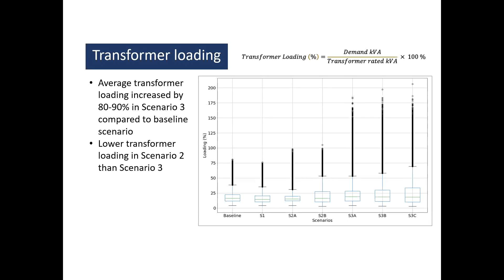The loading is much lower in all scenario 2 cases compared to scenario 3 because of the use of more efficient appliances. And I should also note that in our distribution system model, comparatively fewer residential customers are connected to each transformer with respect to its capacity. And this situation is typically only found in newer distribution systems. So it's notable that we're seeing loading increase despite the higher per customer transformer capacity that we have in our situation. This kind of overloading can adversely affect the life of a transformer, so it's really important to do an in-depth study of the distribution system impacts before you embark on electrifying a residential community. Next slide, please.